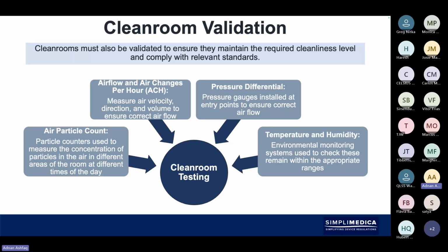So you've got to look at airflow and air changes, looking at the air velocity, looking at direction, the volume of the correct flow, pressure differentials that can also be affected, and temperature and humidity can be affected by the pressure in the external environment.